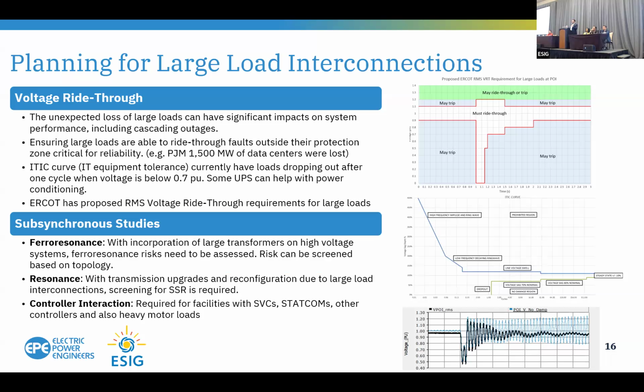So some things to start to consider studying when looking at connections for large loads. Resonance more so will be when you're reconfiguring the system, and controller interaction is really important. And we'll talk about variability in a moment, but for a lot of these data centers, we should be considering when you're looking at reactive compensation, dynamic rather than static.